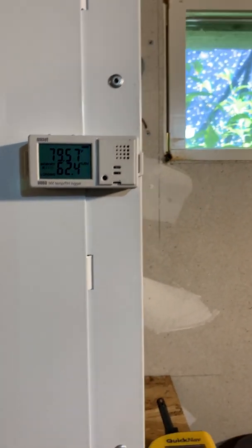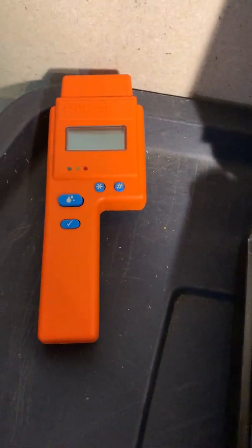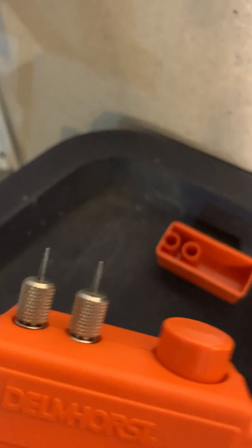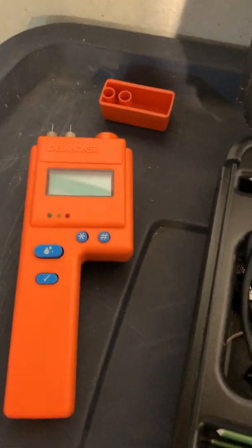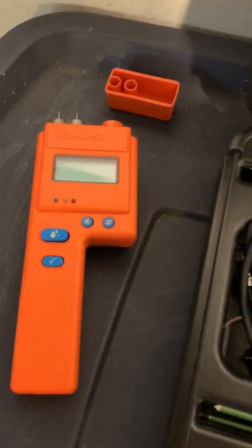And so that's one of the ways that we measure the heat content and the moisture content of the air mass. And what I'm going to do now is show you that we can measure the moisture content of various materials inside buildings, starting off with the wood. So what I'm going to do is show you that with a moisture meter, and we have two of them here. This is the Delmhorst BD2100, which measures moisture content by weight. There are two pins, and this is all covered in material that you're reading as part of the background for this course as well. But electrical current goes between those two pins, and how much current moves through is proportional to how much moisture is in the wood. And through an algorithm table, you can find out what the percent moisture content is by weight.